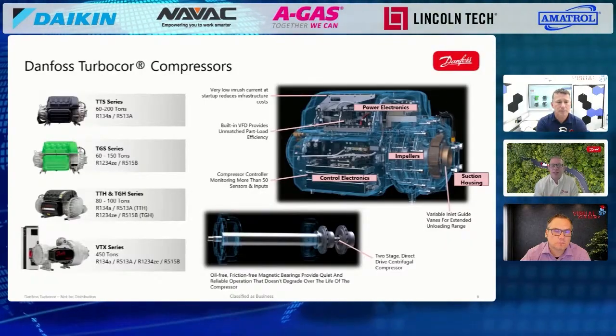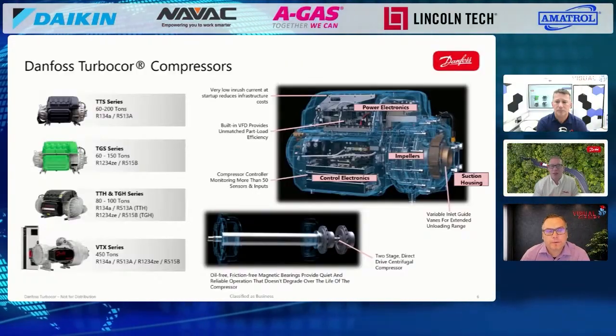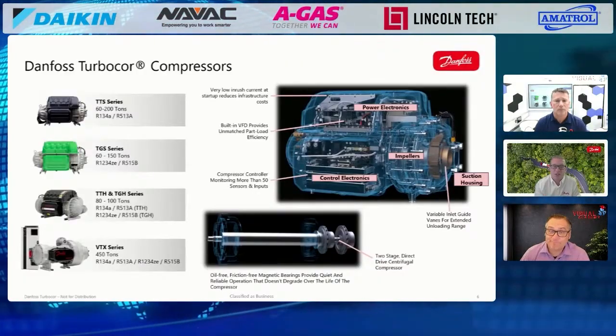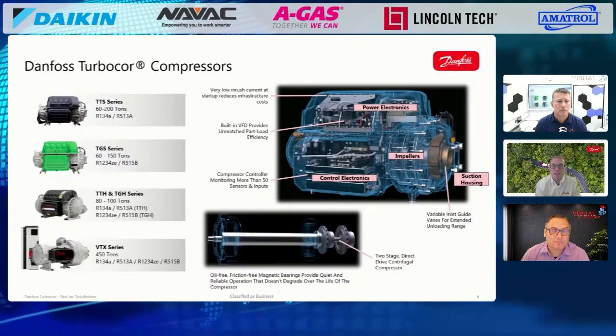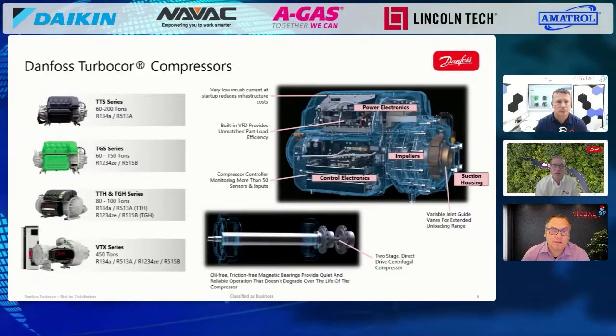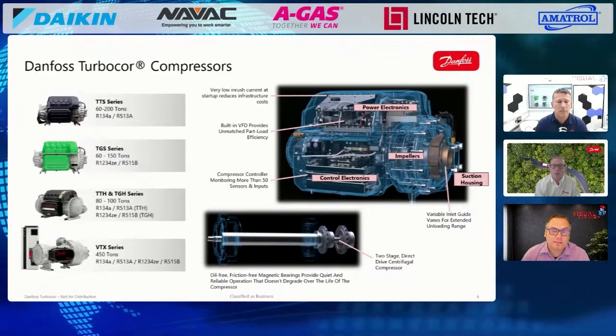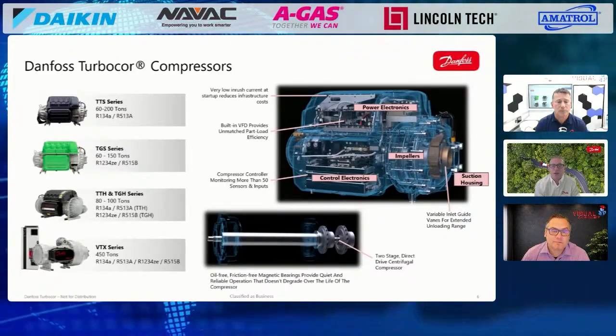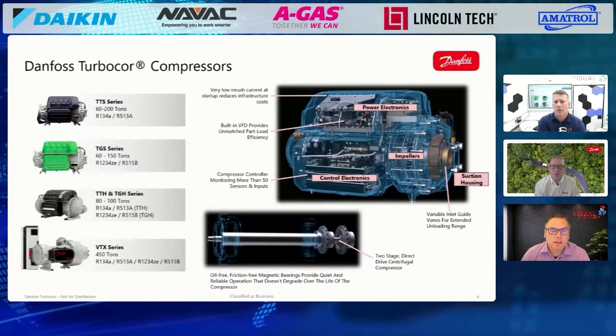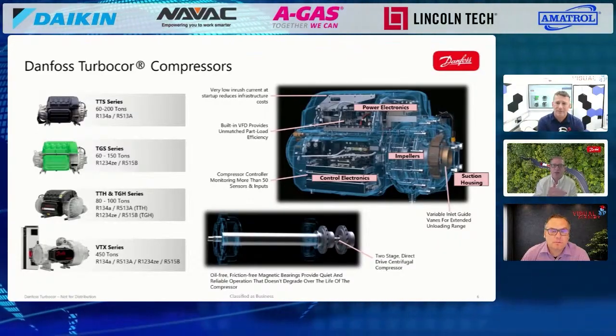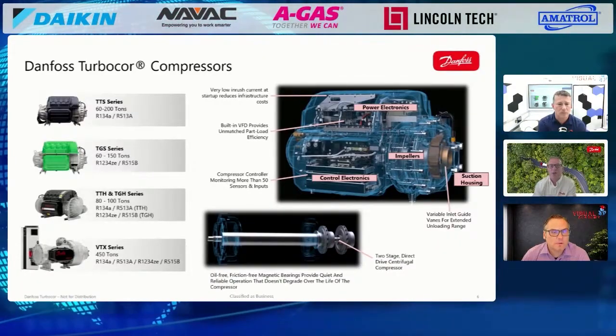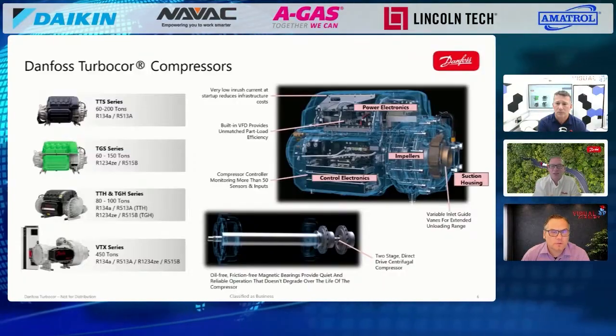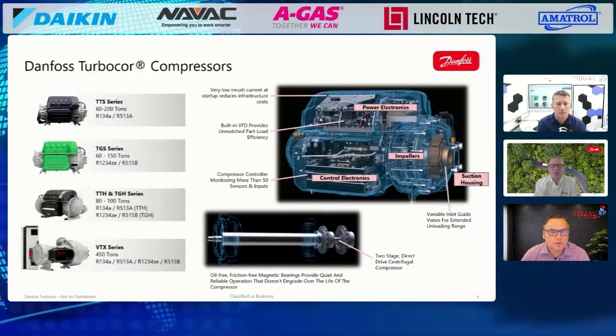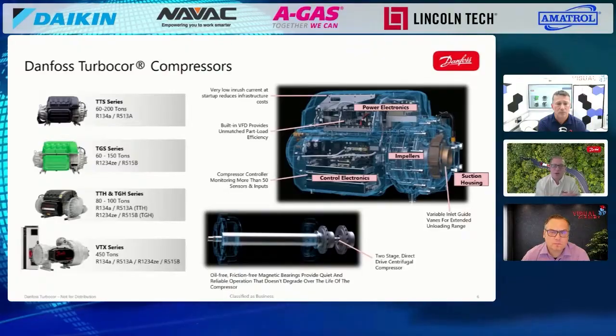And the difference in capacity there is based on the refrigerant characteristics, because 1234ZE and 515B are lower density, lower pressure refrigerants than 513A. So you lose a little bit of capacity through the refrigerant characteristics. Interesting. And then we have a bunch of different models within that TTS series and TGS series that we can customize what we call the aero of the compressor.